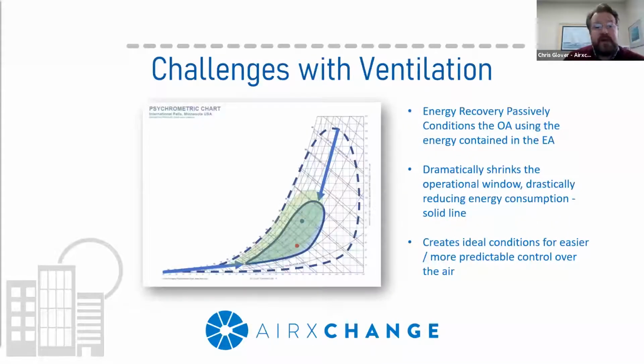So, an energy recovery component is generally just a fancy name for an air-to-air heat exchanger. The easiest way I can describe the process is that all year long, all this device wants to do is bring the outside air as close as it possibly can to the indoor building condition. And depending upon how effective that device is determines how close it gets to those points. It's a passive process, so it only requires a difference in temperature and humidity to perform this work. There's no mixing of air taking place, except for the small amount of seal leakage due to differential pressure. So it's all thermal energy or latent energy that's being transferred.